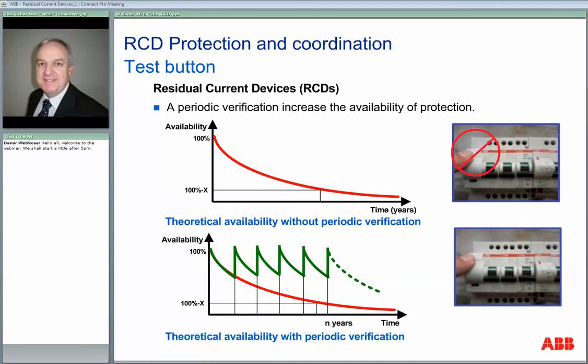Will it actually operate when it's asked to? If it hasn't had to do something for 20 years, you can't guarantee it. So it's a great idea that the device is switched every so often to make sure that the device is exercising and things are working. So that's the theory of having the test button and requiring that it should be operated.